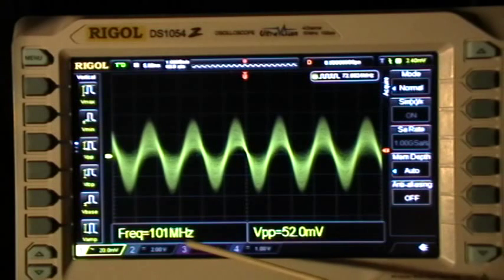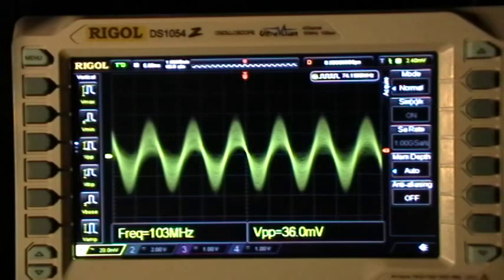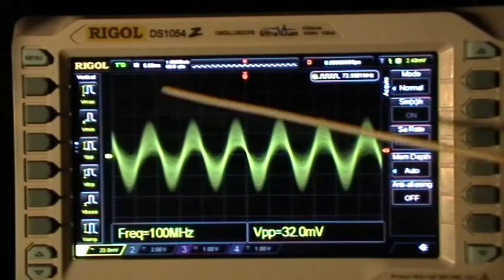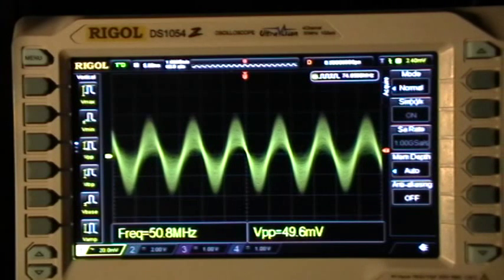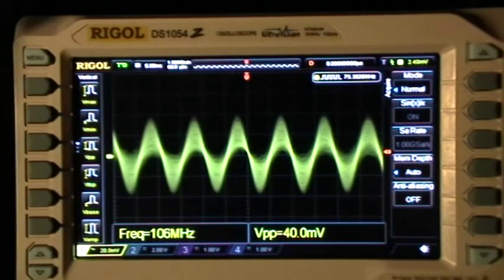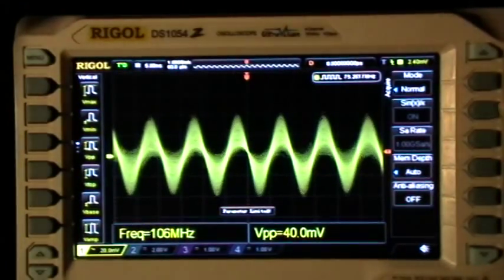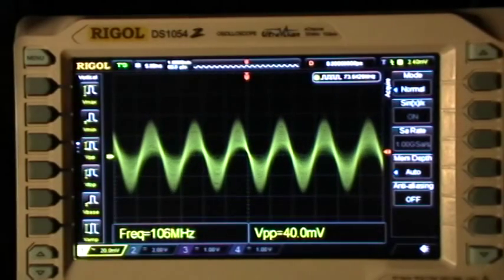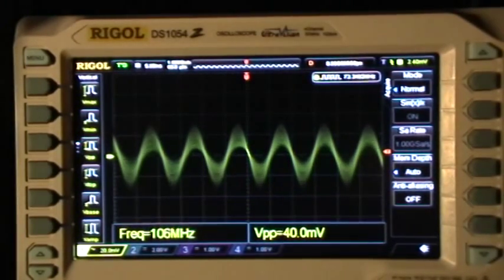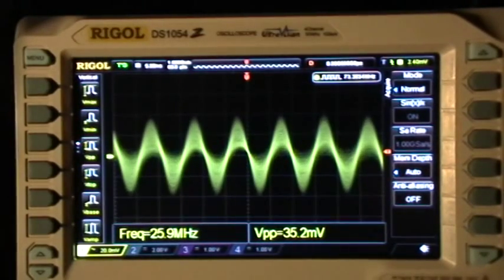At 5 nanoseconds, you can see we still have an unstable frequency here and also up in the hardware frequency counter. There's a lot of jitter in amplitude. I'm going to turn the multifunction knob, which is in the default mode of intensity variation — brighter and brighter, that's as bright as it'll get, then dimmer and dimmer. Now you can see that nice, almost analog-like variable intensity display.